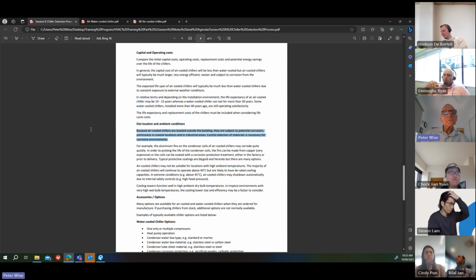Site location and ambient conditions. Because air-cooled chillers are located outside the building, they're subject to potential corrosion, particularly in coastal locations and industrial areas, where there's a bit of salt in the air or acid from industry. Air-cooled chillers can corrode quite rapidly. Careful selection of materials is necessary for corrosive environments.